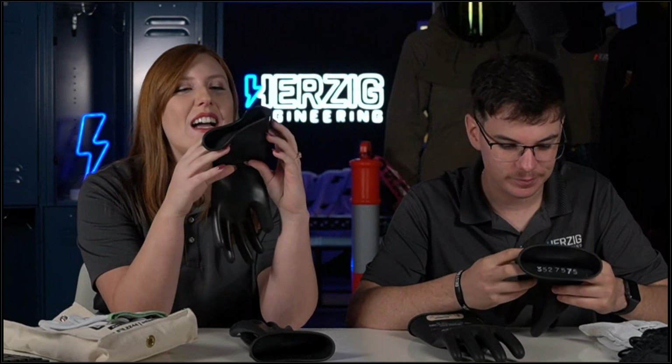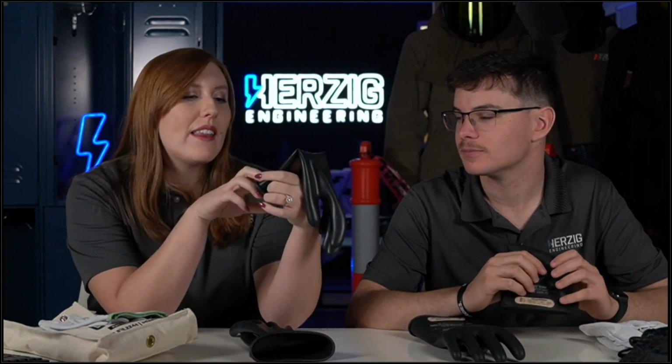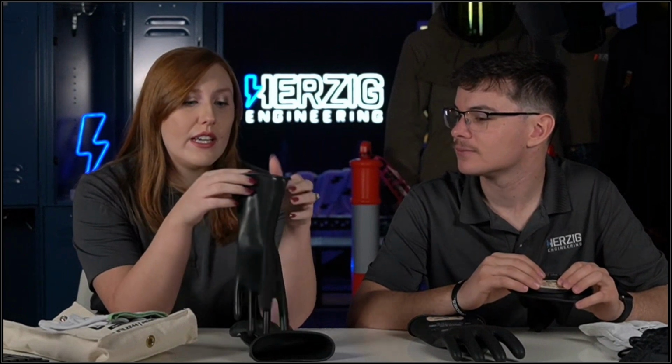When were they last tested? Mine are out of date. I only use them for training purposes, not actually getting in on equipment. It's a classroom training glove only, and so that's fine. These were tested in May of 2021, so I definitely wouldn't use these if I had to get in and do any troubleshooting, or even hands-on training with real equipment, not simulated. But yours were tested November 16th, so they're fairly new. So like you said, April. I have time to use these.